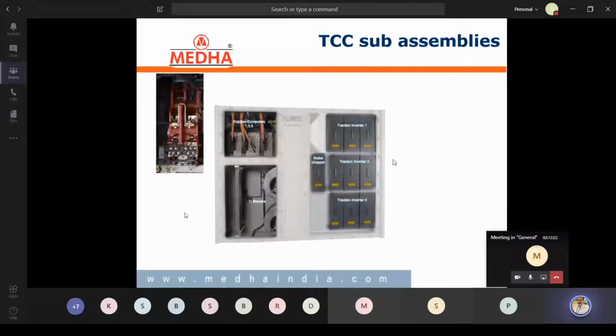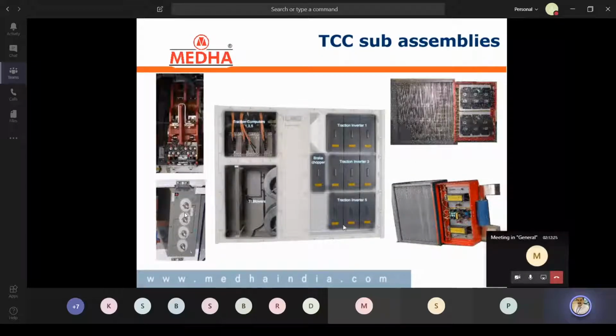So here we can find the open view, where internally we can find the computer section, blower section, inverter section, inverter phase module. Three phase modules form an inverter. So this side 3 inverters and opposite side 3 inverters, total 6. So independent motor control. And one common phase module, that is for brake chopper operation. Okay. So total 19 phase modules will be there. 18 phase modules for the traction converter and 1 phase module for the brake chopper.